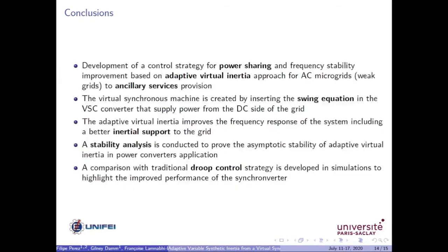In conclusion, we could design a control strategy for power sharing between grids composed of power converters, and we improve the frequency stability of the system based on an adaptive virtual inertia approach for microgrids or weak grids. We're able to provide ancillary services. Also, the virtual synchronous machine is created inserting the swing equation of the voltage source converter that supply power to the AC grid from the DC side of the microgrid. The adaptive virtual inertia improves the frequency response and is able to provide inertial support to this grid.